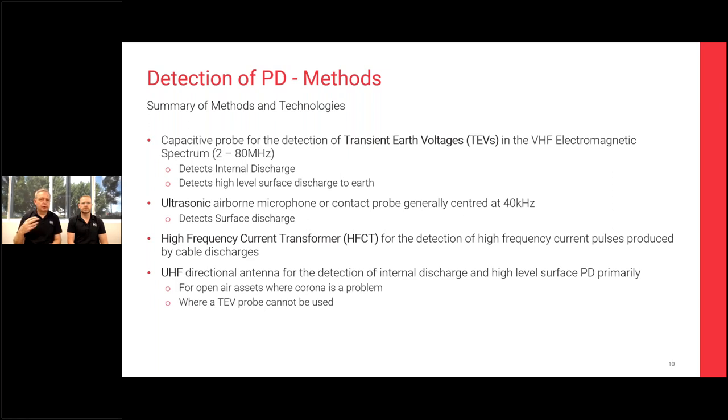This was a technique that was developed back in the days where we had the bitumen filled cable boxes and things like that. So the primary cause of disruptive failure was these internal void type discharges. So TEV is the technique that we use for that. It will also detect high level surface discharge to earth. So if you've got a high component to earth, then the TEV technique comes into its own for that as well.